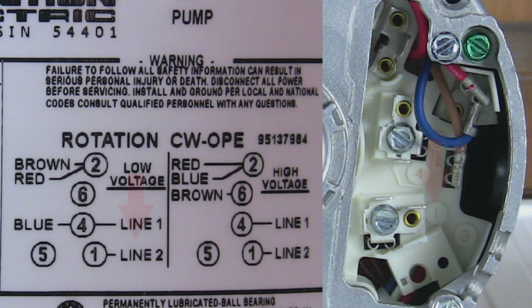Number 6. Locate the white or neutral wire coming from the conduit. This wire is referred to as line 2 on the diagram and is attached to terminal 1. Number 7. Locate the black or hot wire coming from the conduit. This wire is referred to as line 1 in the wiring diagram and is attached to terminal 4. For attaching this motor to 230 volts, follow the same process completed here, but be sure to follow the high voltage diagram. Once wiring is completed, reattach the access cover and reapply power to the machine.